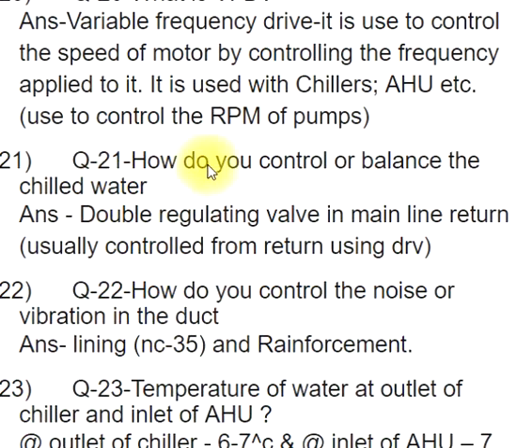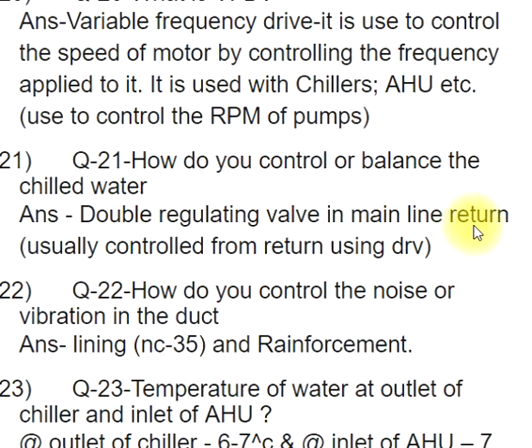Q21: How do you control or balance the chilled water? ANS: Using a double regulating valve in the mainline return — usually controlled from the return using DRV.